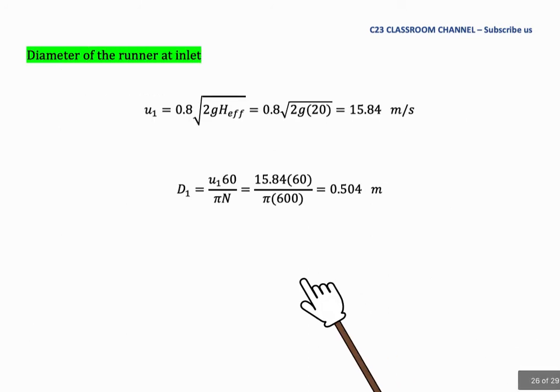Now we are calculating diameter of the runner at inlet. The equation that has diameter and can solve this problem is from U equal to pi dn over 60. We rearrange that equation. We can write D1 equal to U1 times 60 over pi N. To substitute this equation, we need to know the value of U1.